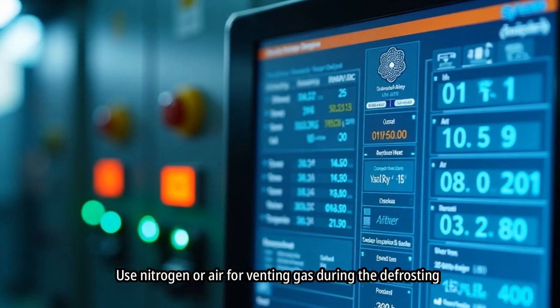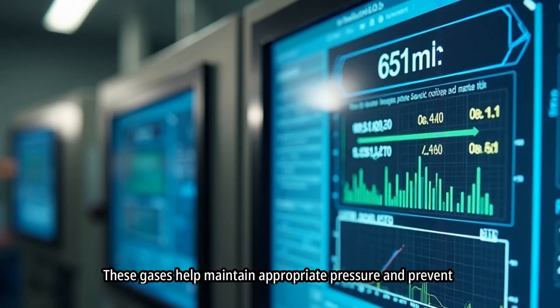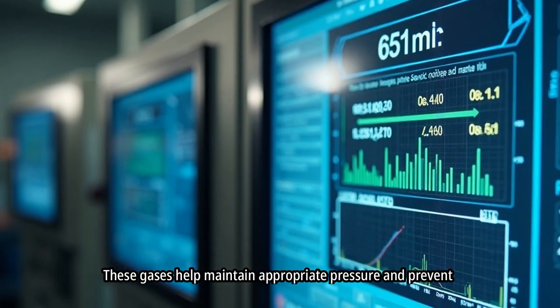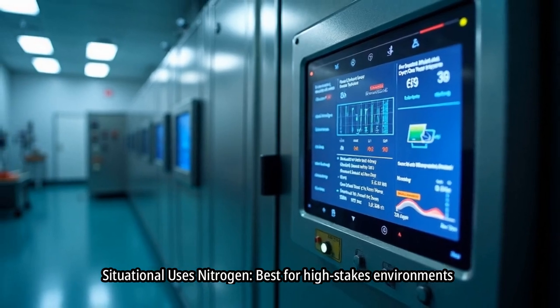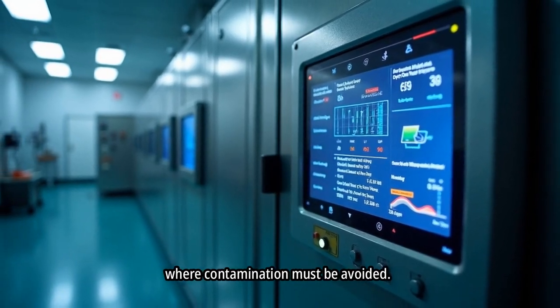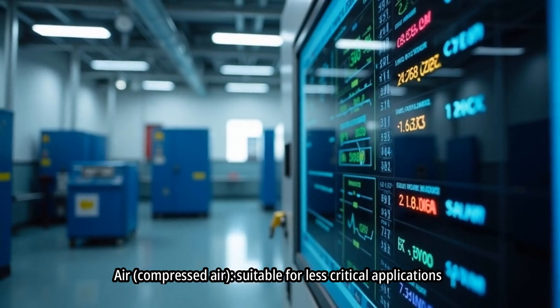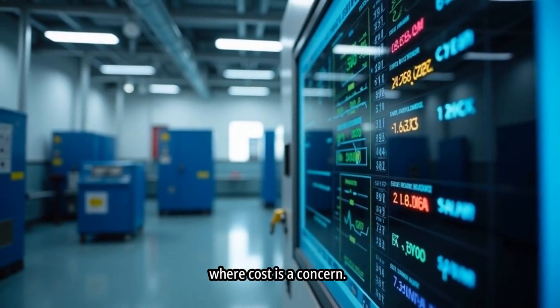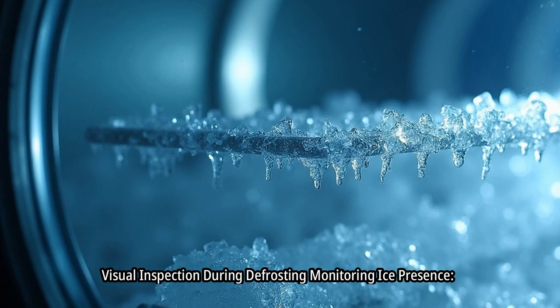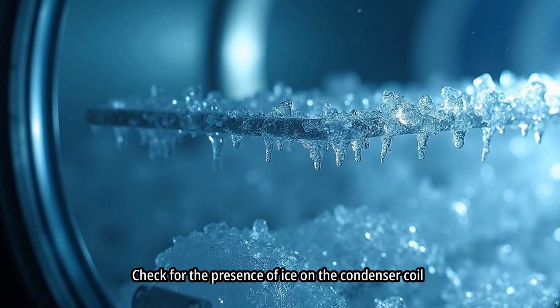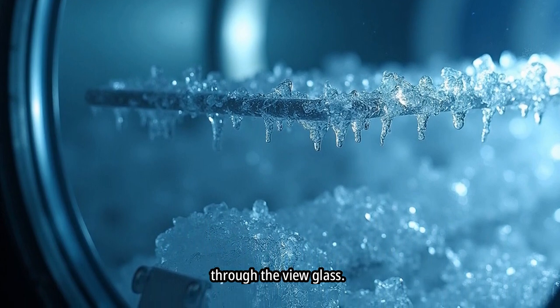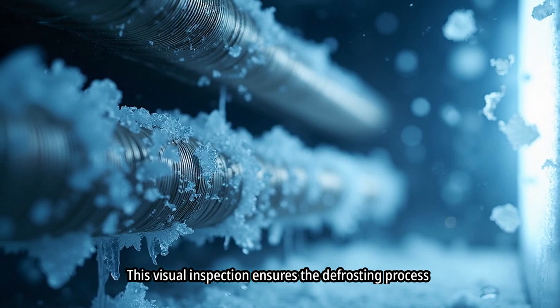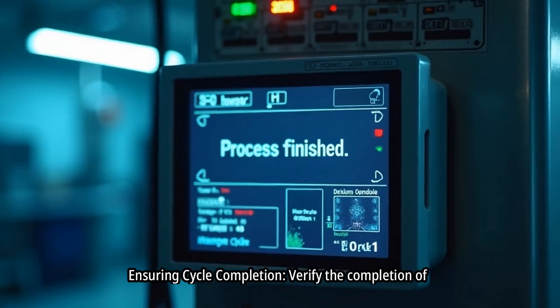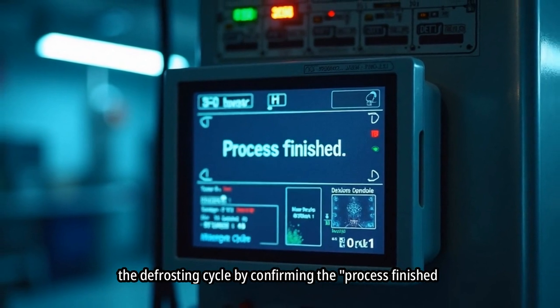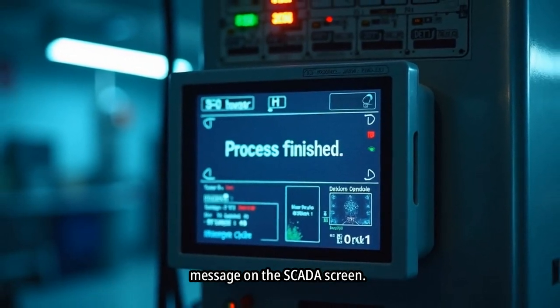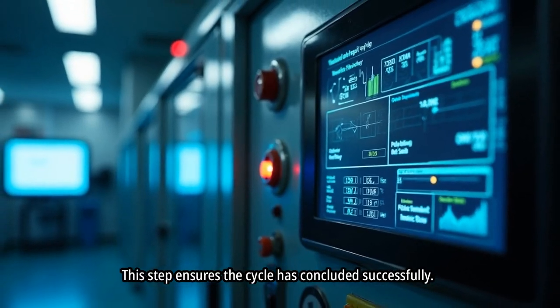Additional functions during defrosting: venting gas options. Use nitrogen or air for venting gas during the defrosting process. These gases help maintain appropriate pressure and prevent contamination. Situational use: nitrogen is best for high-stakes environments where contamination must be avoided. Air, compressed air, is suitable for less critical applications where cost is a concern. Visual inspection during defrosting: monitoring ice presence. Check for the presence of ice on the condenser coil through the view glass. This visual inspection ensures the defrosting process is proceeding correctly. Ensuring cycle completion: verify the completion of the defrosting cycle by confirming the process finished message on the SCADA screen. This step ensures the cycle has concluded successfully.